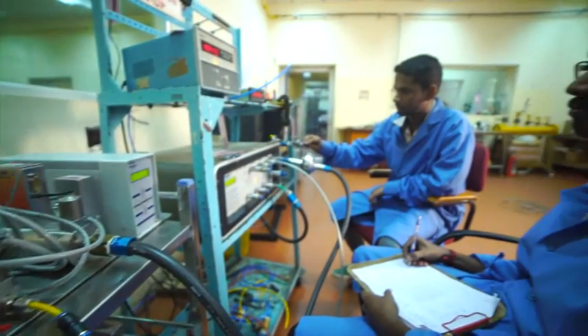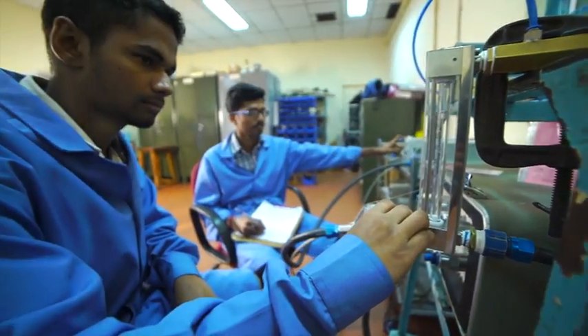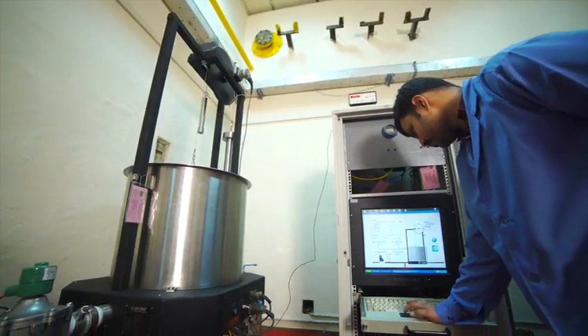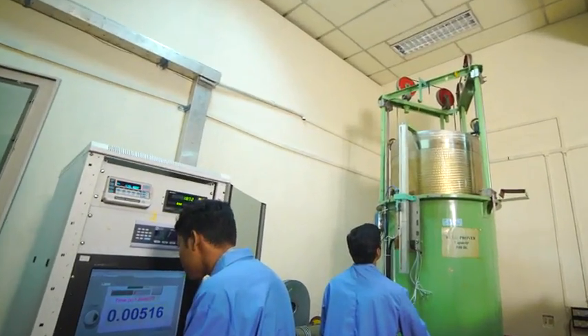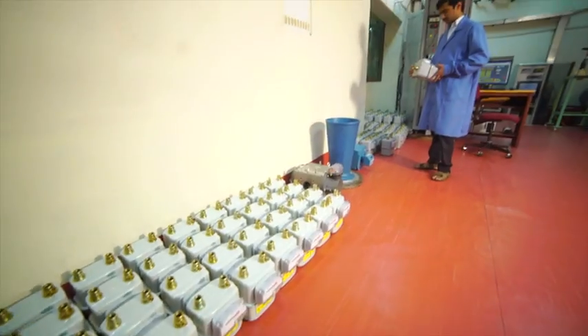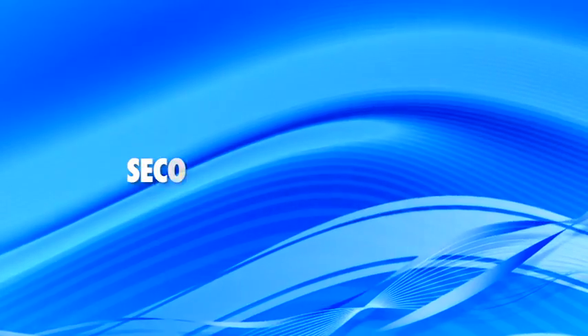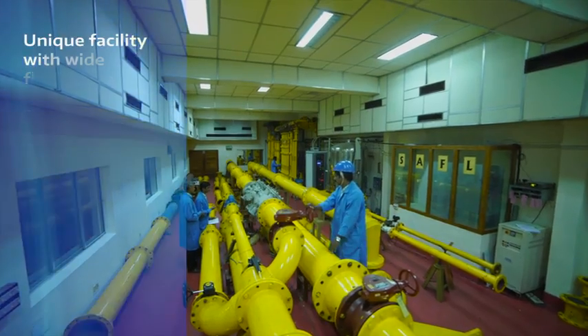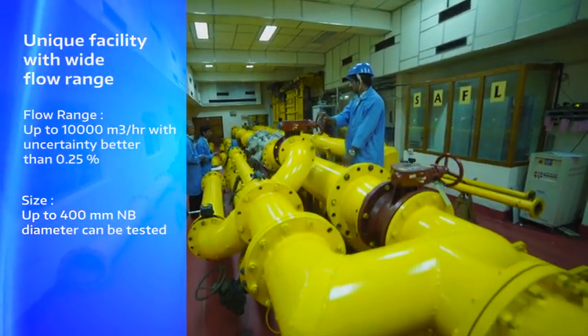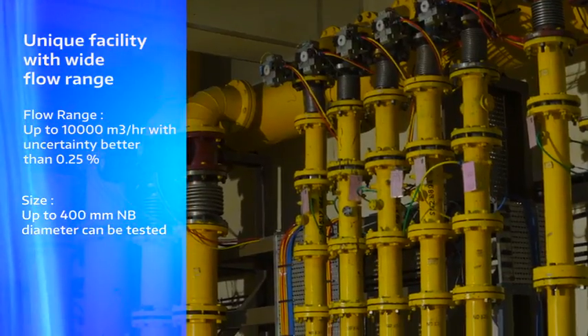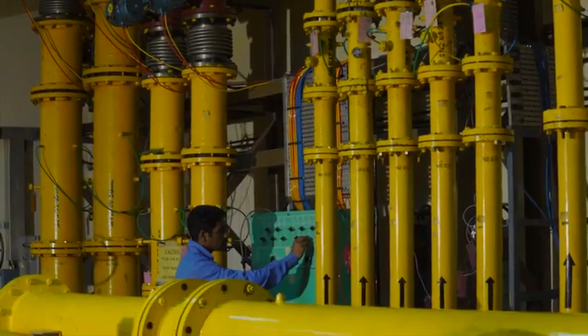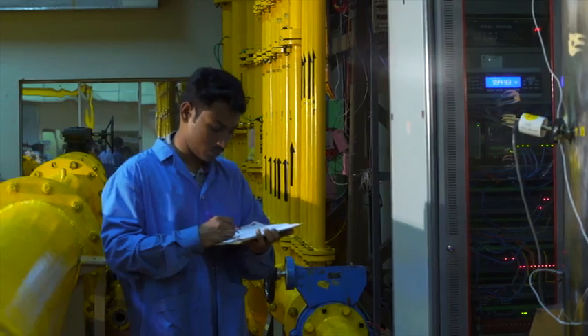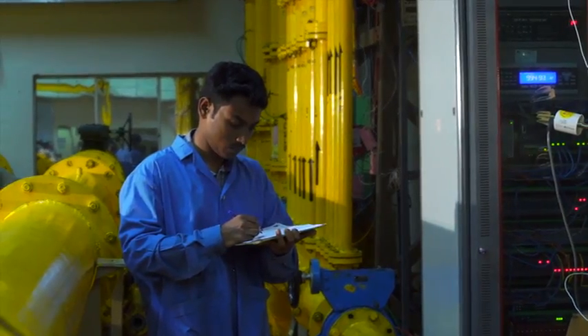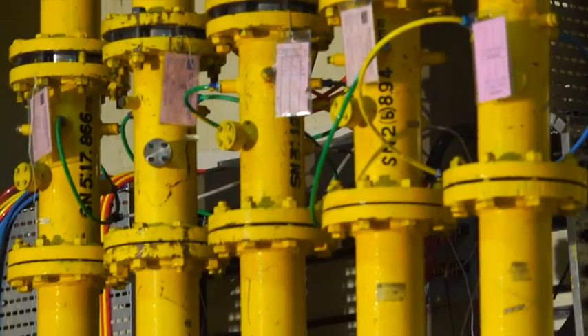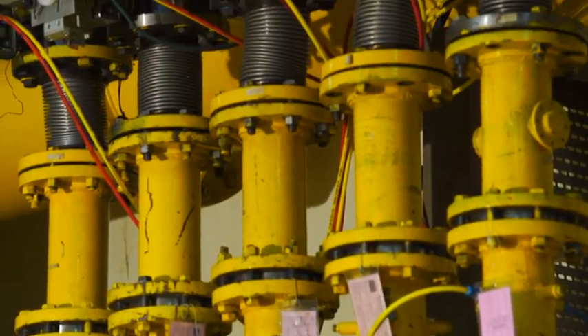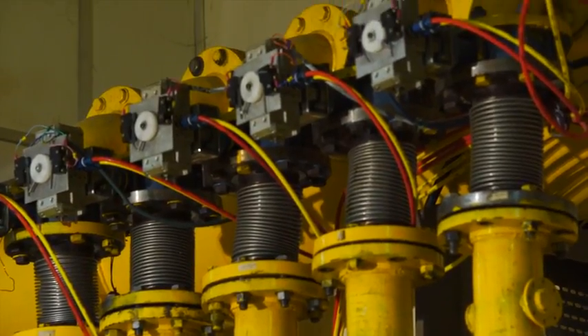of various capacities for precise flow measurement and calibration of flow meters at low pressure with a flow range of 0.05 to 40 cubic meter per hour with uncertainty better than 0.2%. The secondary airflow lab is operating at near atmospheric pressure and has critical flow venturi or sonic nozzles as reference standard. Calibration of flow meters can be done up to a maximum flow range of 10,000 cubic meter per hour with uncertainty better than 0.25%. The adjoining chiller plant controls the air temperature with ±1 degree centigrade during calibration.